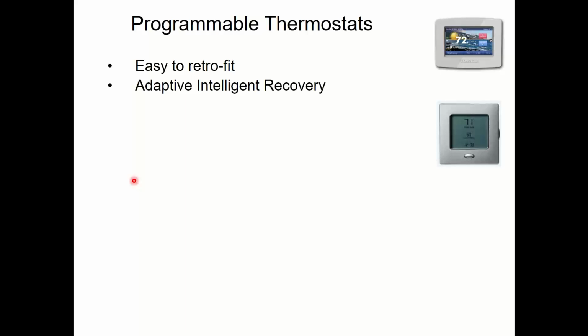Every time it doesn't start as early as you would have put in, it's saving you minutes of runtime on each of those days, which saves you hours a year, which saves you tangible dollars. It's super easy to do, and every high-end stat has it. It costs like $10 more than a regular stat. You have to have two-stage thermostats. All thermostats at commercial buildings need to be two-stage stats. It's going to be required when we talk about the integrated economizer in a couple minutes. So for right now, just know that it has to be two-stage. I'll explain why in a little bit.